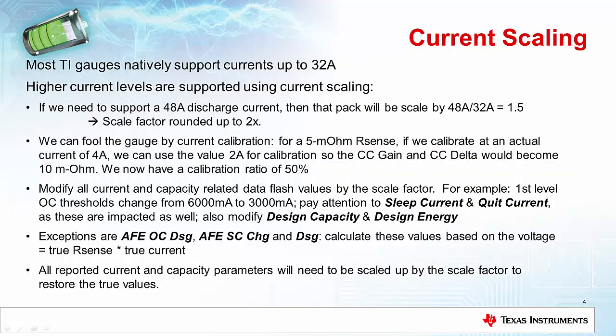And then you basically fool the gauge when you're doing the current calibration. For example, if you're using a 5 milliohm sense resistor, if you're actually using a current of 4 amps, you actually tell the gauge that you're really using a current of 2 amps during your calibration. And so then when it calculates the CC gain and CC delta, they calculate out thinking that you were using a sense resistor of 10 milliohms. And so then you have a calibration ratio of 50%.